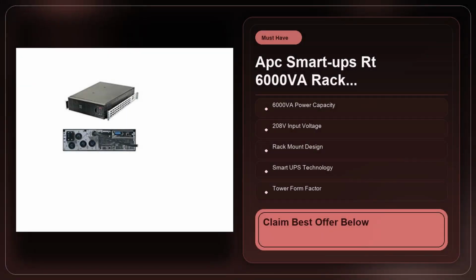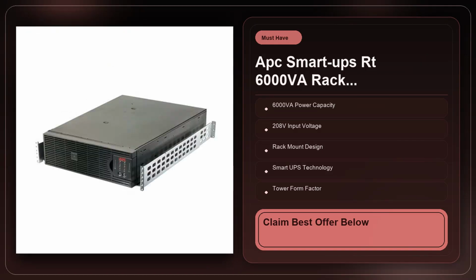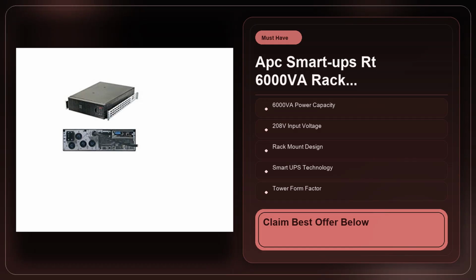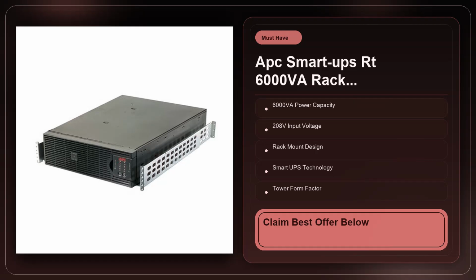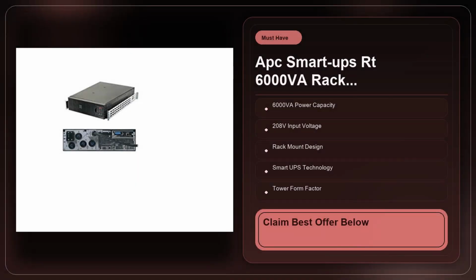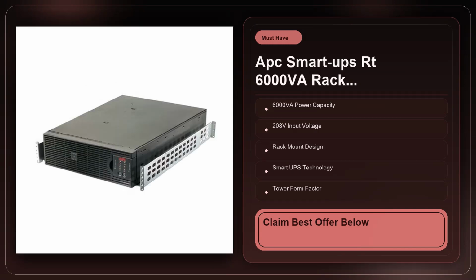Third, the Smart UPS RT includes automatic voltage regulation, AVR, that smooths out minor sags and spikes without dipping into battery power. In a typical office building where the power quality swings between 190V and 230V, the AVR kept the output steady, saving battery life for the real emergency. Finally, the rack mount design includes hot swap battery modules. If your maintenance window is limited, you can replace a depleted battery without powering down the entire UPS, a level of convenience you rarely get with smaller, sealed lead-acid units.